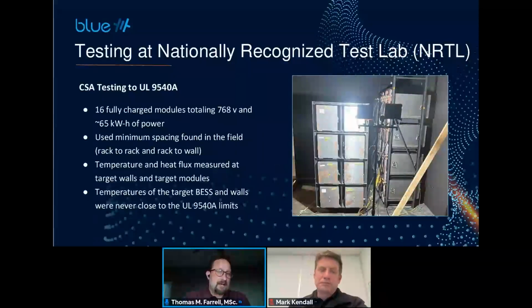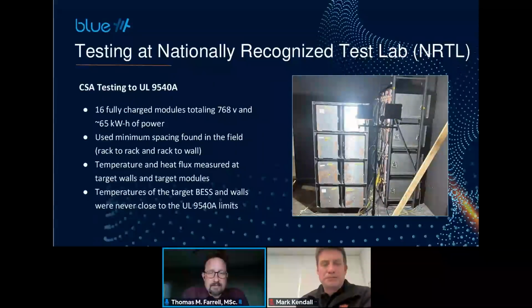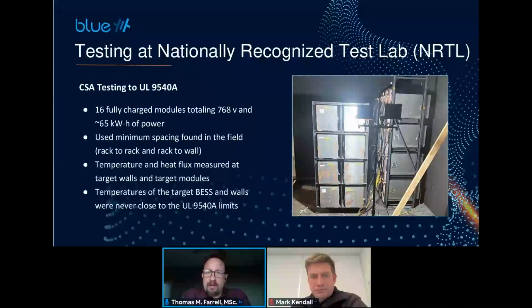And in this particular test, when they ran one of these modules, and again, these racks were fully populated, they ran one module in the middle of this rack into thermal runaway using the same methods that we use at Fike. Blue was able to control that test, and the temperatures both at the target walls and the target ESS units above and to the side were never close to the UL 9540A limits. And again, looking at that yardstick measure of around 97 degrees Celsius above the temperature at start.